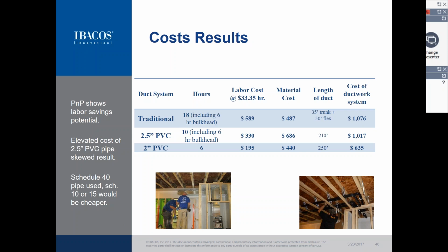We had a basic labor cost assumption. The material costs showed some interesting outcomes: the 2.5-inch PVC was significantly more expensive, largely because that diameter isn't readily available—it's more of a specialty size. Also, Schedule 40 pipe was used as a readily available surrogate material, but we envision this duct system could use a much thinner-walled material, which could bring costs down further. So when you look at total numbers, partly because of that elevated material cost, the 2.5-inch system and the traditional system had similar total costs.